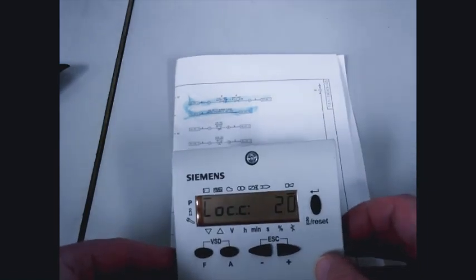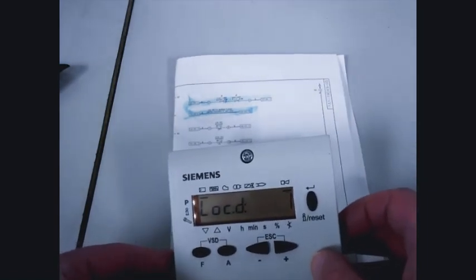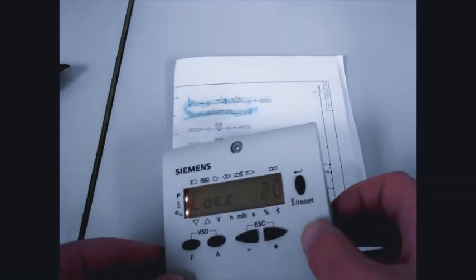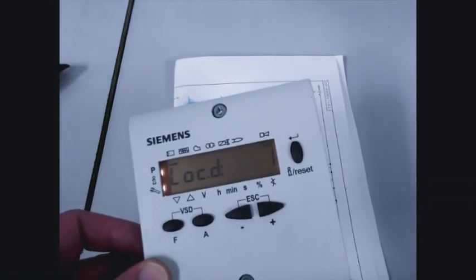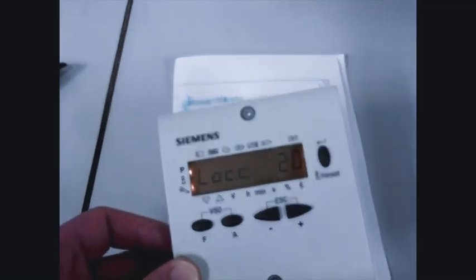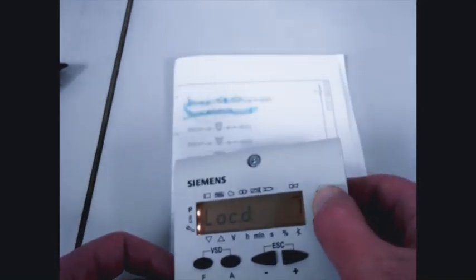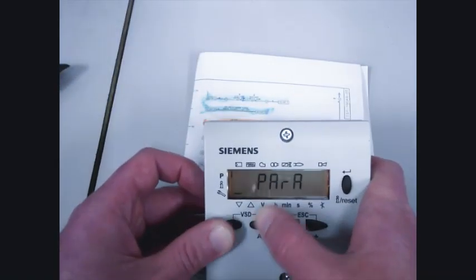We get a fault message: lockout code 20, diagnostic 1. We turn the burner switch off and reset the error. Ensure that the low gas pressure switch is made and that we have power to X501.2. Get back into commissioning.